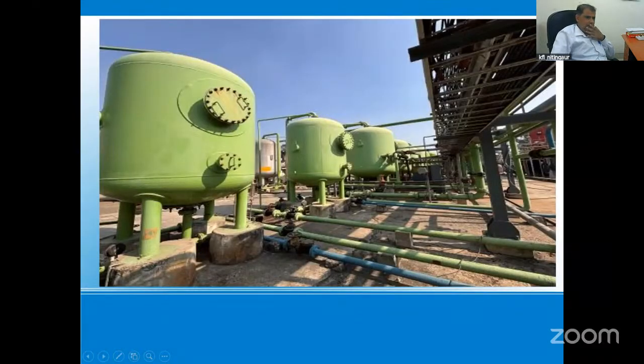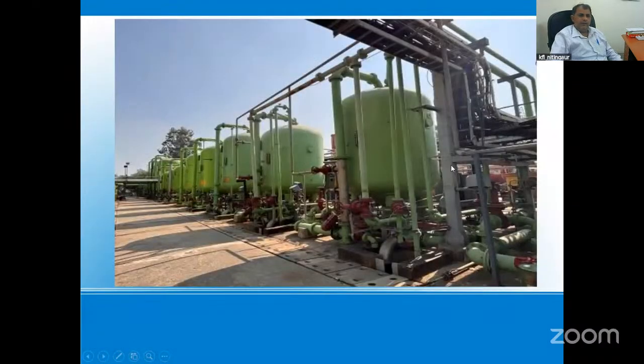This is our setup plant for DM water. All the vessels have their own properties. Demineralization of raw water is not an easy task. How many processes are required? During the demineralization process, we remove the cations and anions present in the water. For the removal of cations, a separate unit is there. For the removal of anions, a separate unit is there. Also, we have a degasser tower to remove the CO2 present in the raw water.